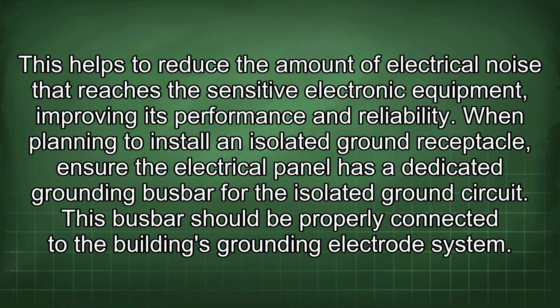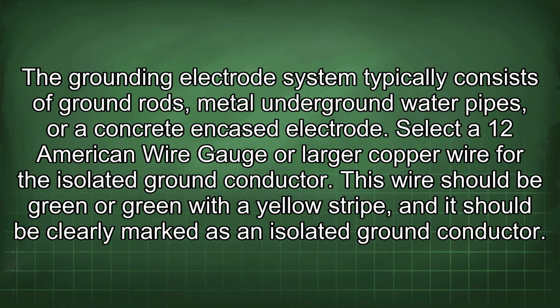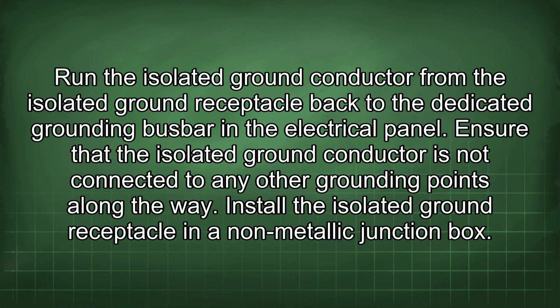When planning to install an isolated ground receptacle, ensure the electrical panel has a dedicated grounding busbar for the isolated ground circuit. This busbar should be properly connected to the building's grounding electrode system. The grounding electrode system typically consists of ground rods, metal underground water pipes, or a concrete encased electrode. Select a 12 American wire gauge or larger copper wire for the isolated ground conductor. This wire should be green or green with a yellow stripe, and it should be clearly marked as an isolated ground conductor. Run the isolated ground conductor from the isolated ground receptacle back to the dedicated grounding busbar in the electrical panel. Ensure that the isolated ground conductor is not connected to any other grounding points along the way.